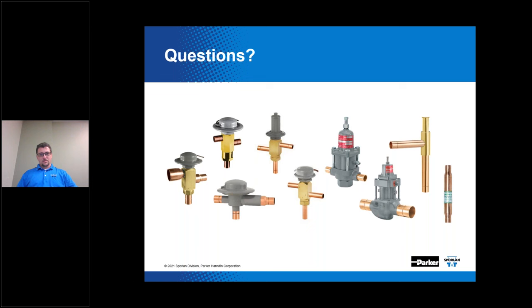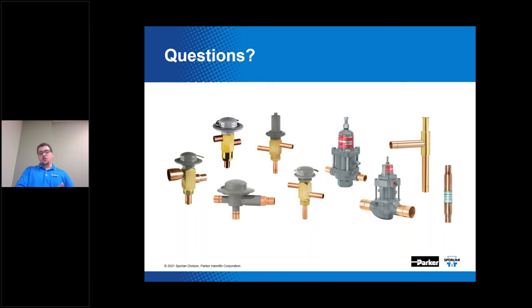Question: What do you recommend as a minimum pressure drop across the expansion valve? For a TEV, I would say no less than around 50 pounds. You need to have enough pressure drop across the downstream distributor, because your total pressure drop is set across the electric expansion valve and the downstream distributor. The pressure drop across the distributor actually determines what the minimum pressure drop is across the expansion valve, so I can't put an exact single number to that.